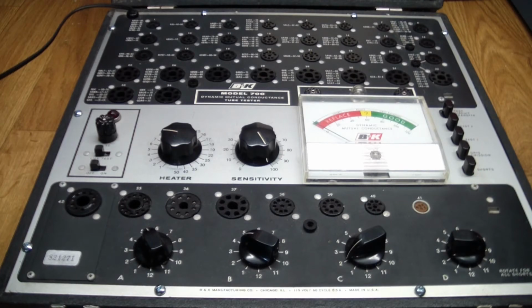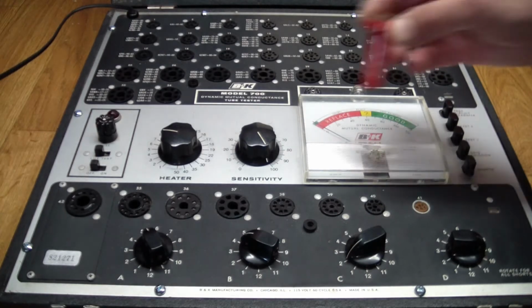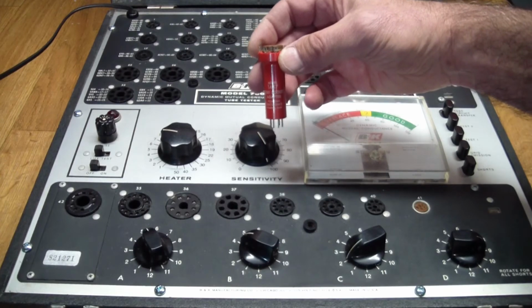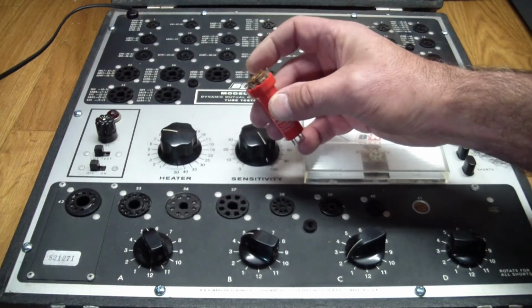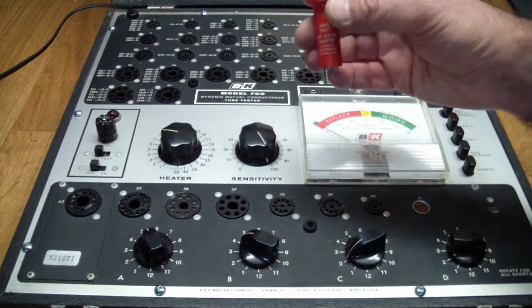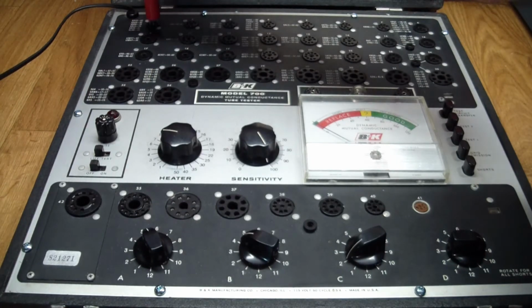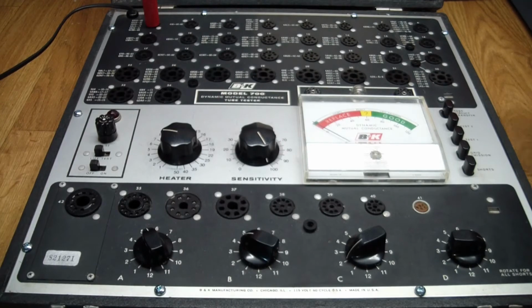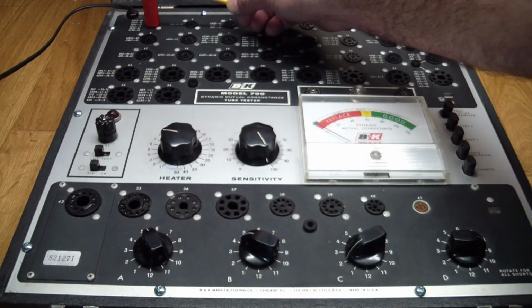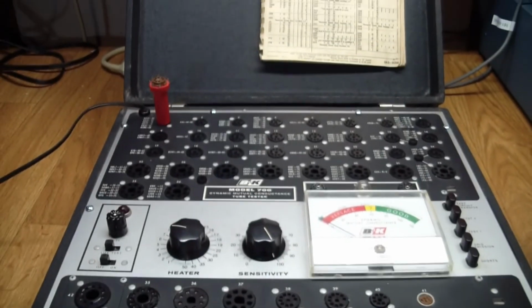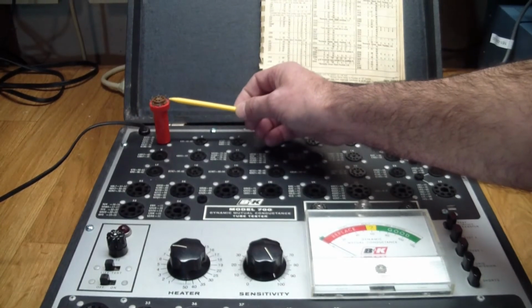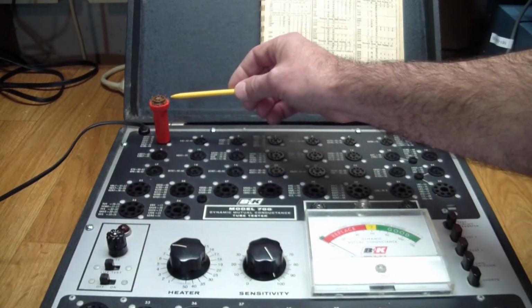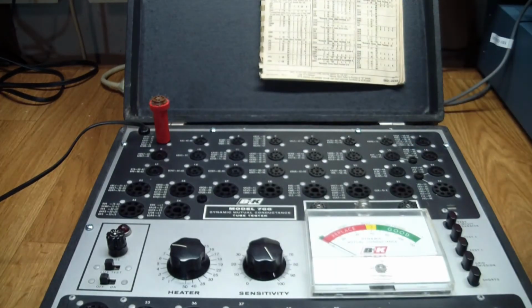Now, in order to test this, you need to make some connections to socket number 1 over here. And what you will need is a tube test adapter socket, which I was lucky enough to find. And this is what it looks like. It plugs into a socket, has another socket on top, but also contacts on the side for you to be able to clip on test leads. So that thing goes in here, and since we're looking at the top of the tube, pin 1 is over here, which you can't see. Pin 1 is over here, and basically goes in a counterclockwise direction to pin 7 over here.